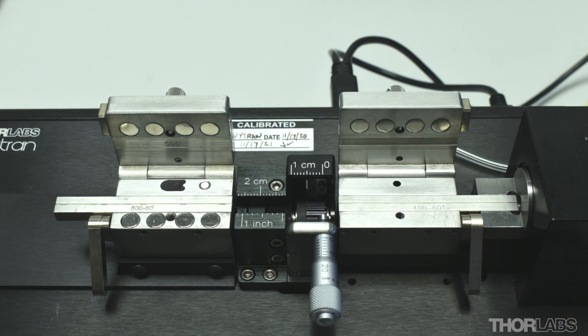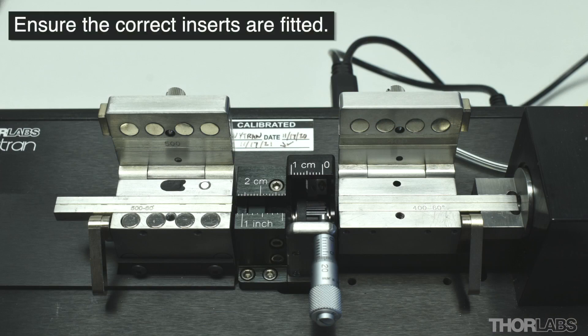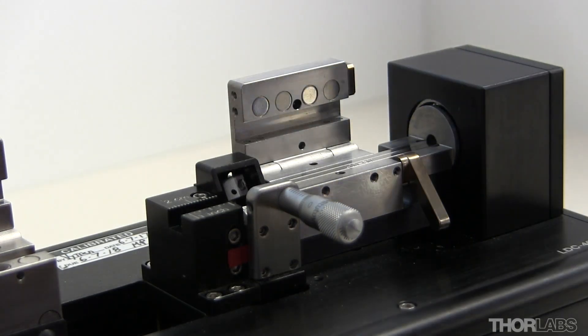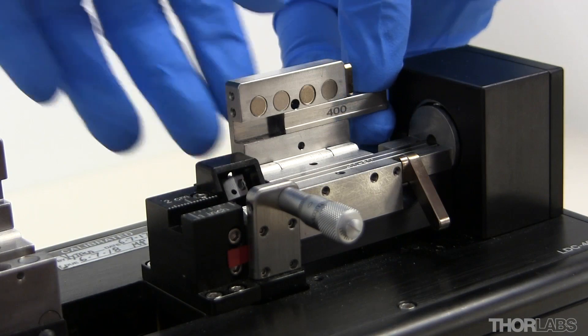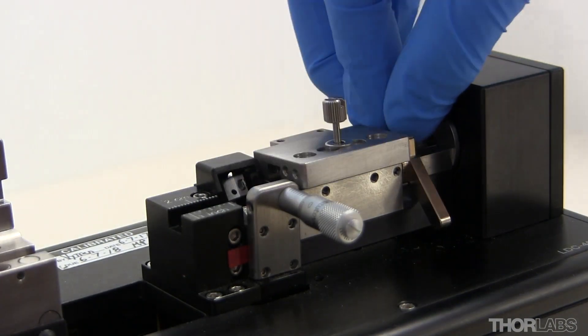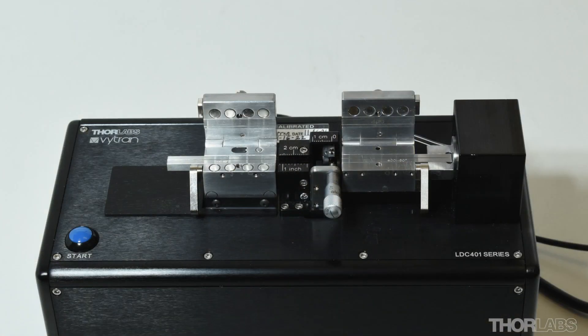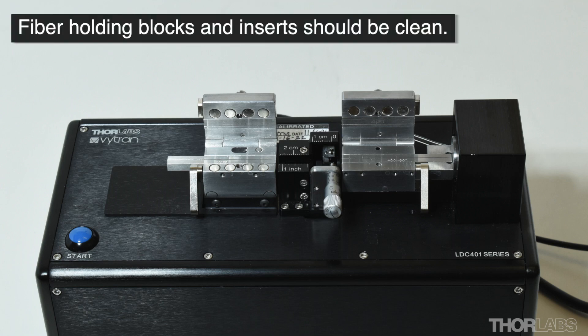If the cleave performance becomes sub-optimal, first ensure that the inserts loaded into the left and right fiber holding blocks are appropriate for the dimensions of the fiber being cleaved. If you have not already watched the video about installing cleaver inserts, click on the annotation to view this first. Now ensure that both the left and right fiber holding blocks and inserts are clean and free from debris. Clean if required.